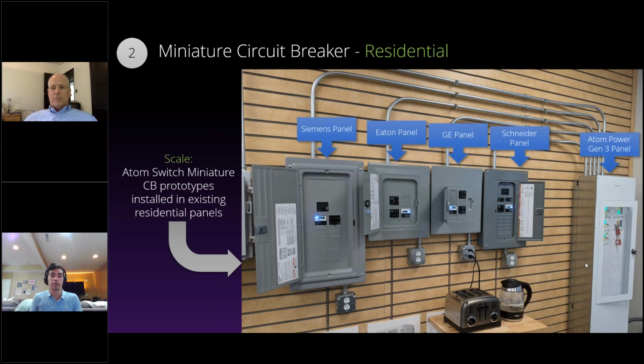But it does have a customizable TCC. So, as a branch device, you want it to trip first, because you want it to coordinate faster than the device upstream from it. So that's great. It'll trip first every time. To coordinate with mechanical devices downstream from it, you'll just need to set the time current curve above that device, which may or may not be possible depending on the ratings of the two devices. So we do have in-depth time current curves available. If you need to do a coordination study, we can help you with that.